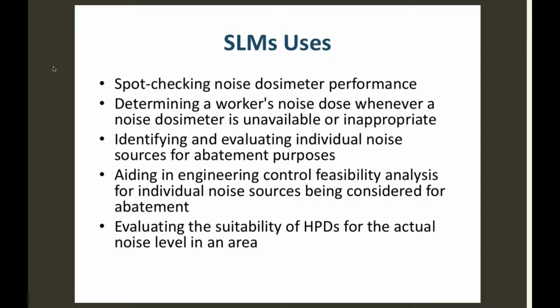Okay, so that dosimeter, that's what OSHA wants to know about. That's what's going to determine whether or not you require a hearing protection program. Whenever you're talking about OSHA permissible exposure levels, you're always talking about specific measurements on the worker, right? So you're not talking about area measurements. In this case, you might use this as a method to check that dosimeter to see if it is reading properly. And we'll take a look at what the difference looks like from these two things.